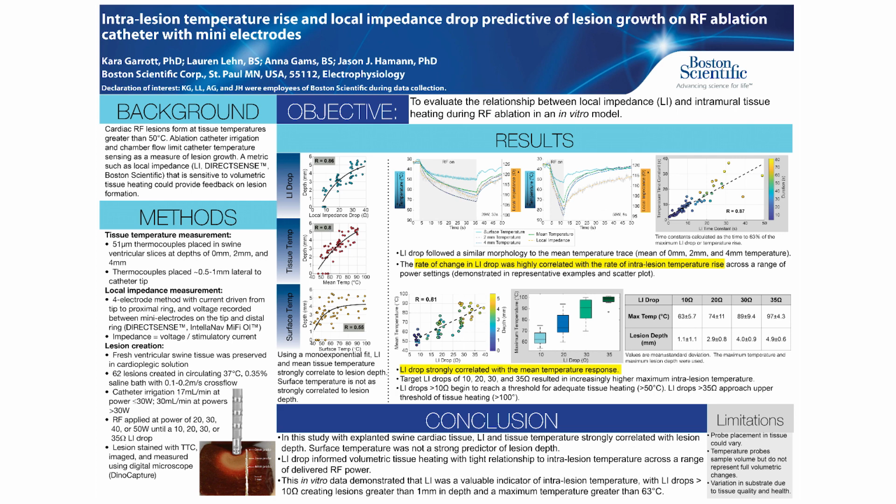collection. The overall objective of this benchtop study was to evaluate the relationship between a local impedance metric and the intramural tissue heating during RF ablation. This was done by using thermocouples embedded within ventricular tissue.